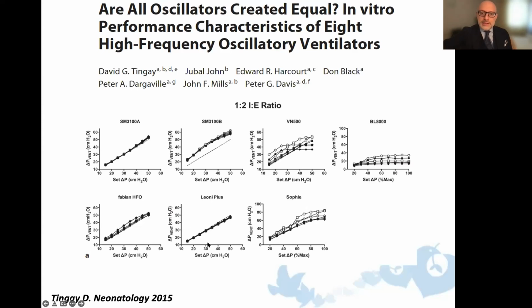You see here, for example, the delta P on the y-axis that is provided by the ventilator compared to the delta P that is set on the machine is very much steady and correlates for most of these ventilators, which is not the case for VN500 because it's a sort of a plateau, and same applies for Sophie, for example, not to mention the old Babylog that you can clearly see provides even lower delta P. And you know the delta P is something that is very much important because it's the main determinant responsible for the production of the stroke volume delivered to the baby, which I don't call tidal volume because we're not providing a tidal ventilation, but still is the small volume that is provided by the cyclic oscillation towards the baby.